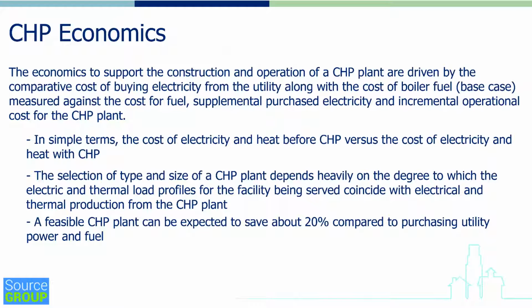CHP Economics. The economics to support the construction and operation of a CHP plant are often driven by the comparative cost of buying electricity from the utility, along with the cost of boiler fuel, referred to as the base case, measured against the cost of fuel, supplemental purchased electricity, and the incremental operating cost of the CHP plant. In simple terms, it's the cost of the electricity and heat before CHP versus the cost of electricity and heat with CHP. And it's that cost delta that determines the savings.